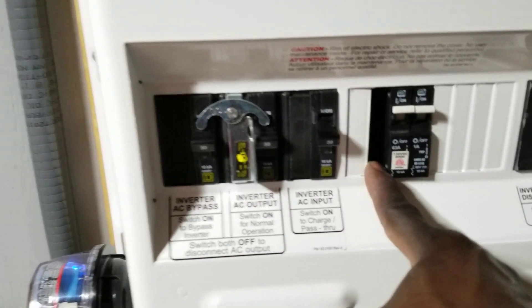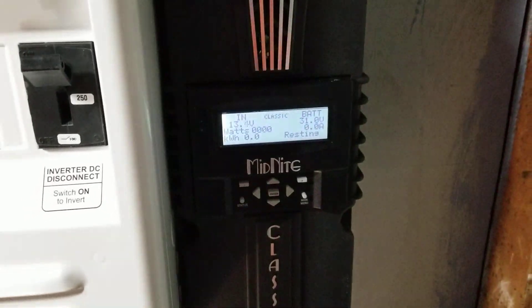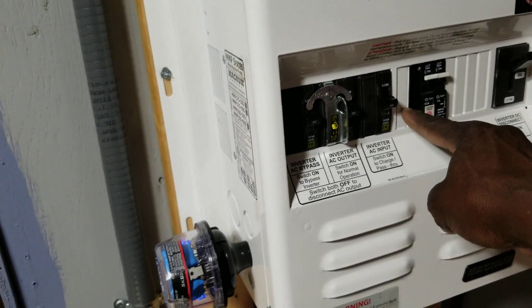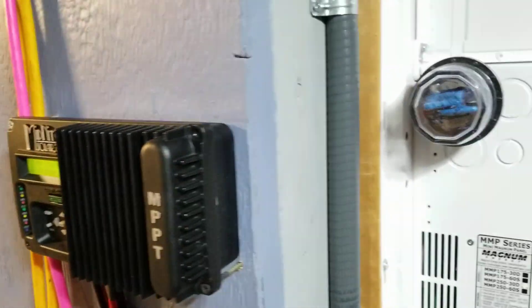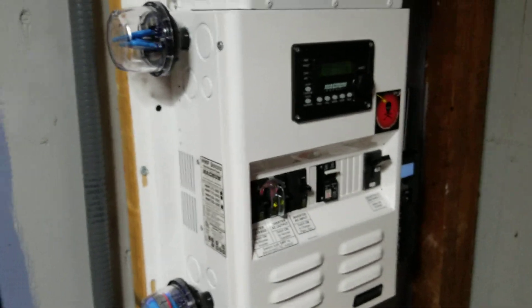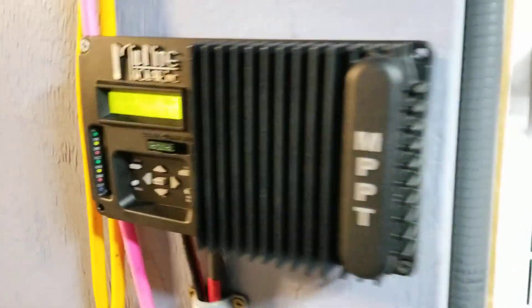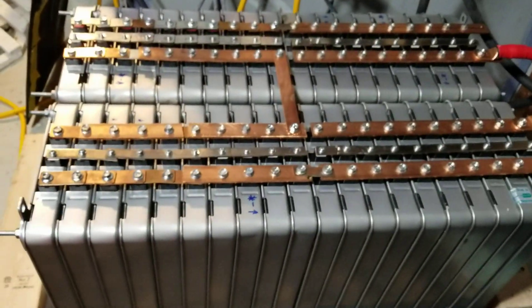We're going to add a 63-amp breaker here for the twin of this, which is the MidNite Classic 250 charge controller. We also need to add breakers for the solar inputs for both controllers. There's a rumor that Dave is thinking about adding a wind turbine, so these breaker slots are good for that too — rated for 30 amps at 150 volts. This is the MidNite Kid, and now we're going to initialize the battery charging.